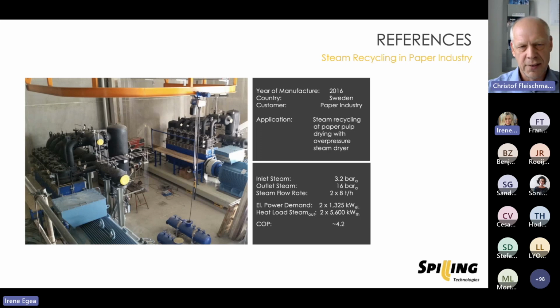And out of this paper pulp comes steam when the product is dried under a certain overpressure, about 3.5 bar. This steam coming out is contaminated. It has to go through a cleaning stage. Finally, 3.2 bar clean steam results from that. And this can now be compressed with our units to the 16 bar.